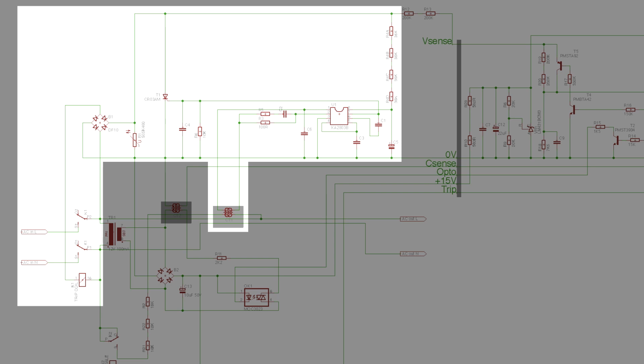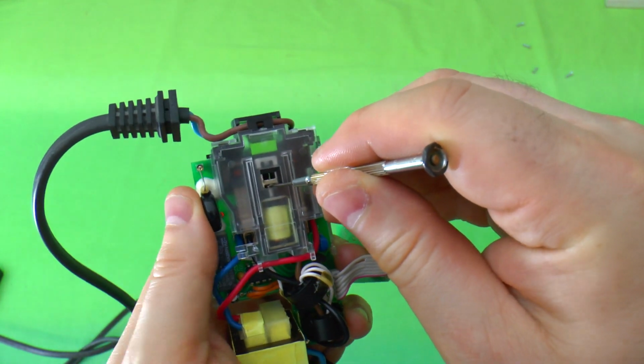If that IC detects an earth leak, it's through the current transformer, basically because it's detected an imbalance. Normally, live and neutral currents are the same and they'll cancel out. If there's a difference, this detects it and trips out. What happens is that it actually trips out that thyristor, the SCR, over towards the left, and that basically shorts out that chip's own power supply. At first I was thinking, that's weird, I don't see how it worked that way. But if you look at the supply to that circuit, which comes from the bridge rectifier, that circuit actually comes through the trip coil. So if that SCR closes and shorts out the power supply for the chip, all the current all of a sudden, instead of being just enough to keep the circuit working, the full load will go straight to that trip coil, pulling in the coil and releasing the breaker.